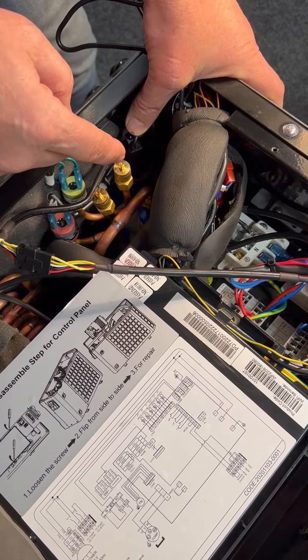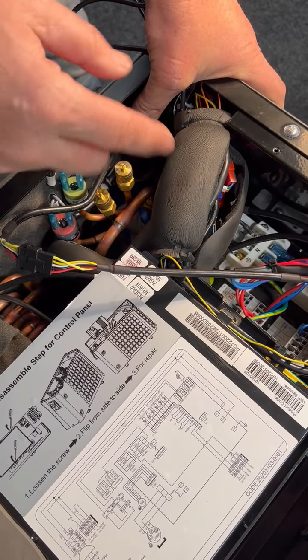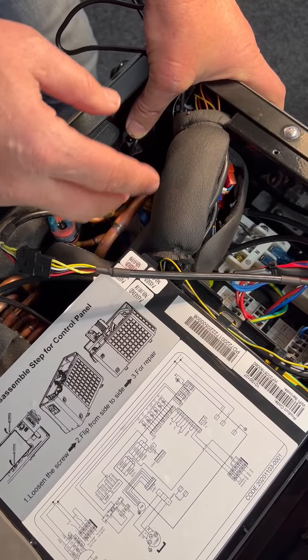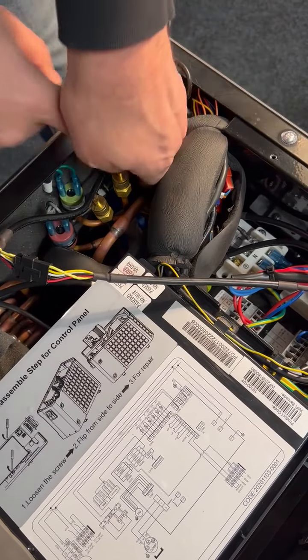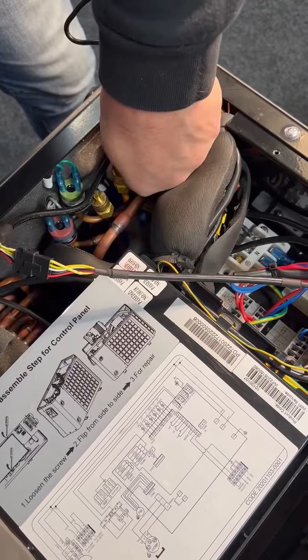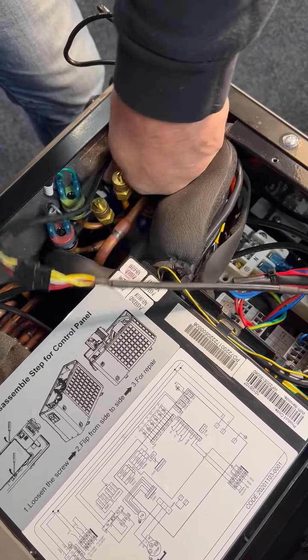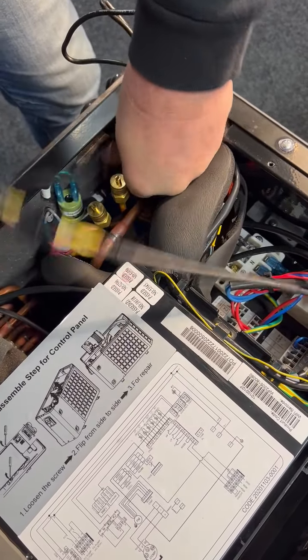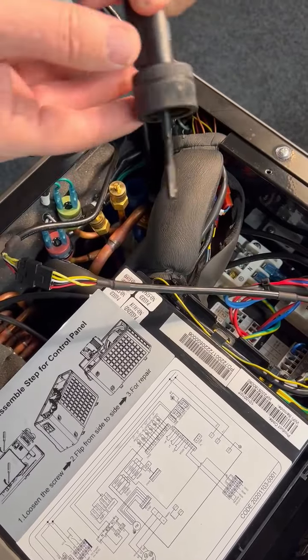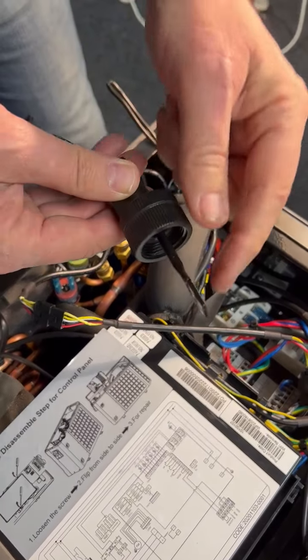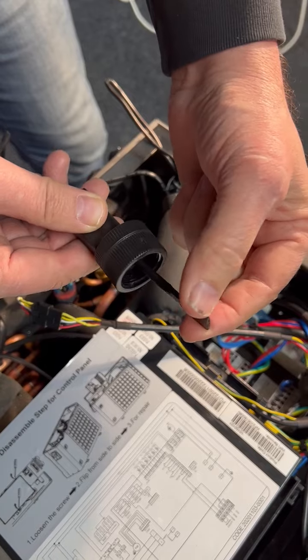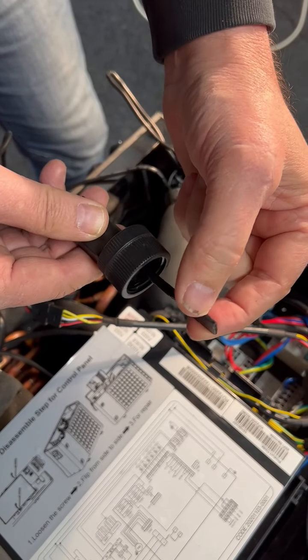So we need to remove the flow switch. First, you need to turn all the water pumps off so you've got no pressurized water. And all you do is lean down in here, and they're all hand tight because they've got an O-ring. And you just undo that nut, and you actually, here we go, we pull the flow switch out, and as you can see, there's a little paddle there, and obviously the contact is broken in there.